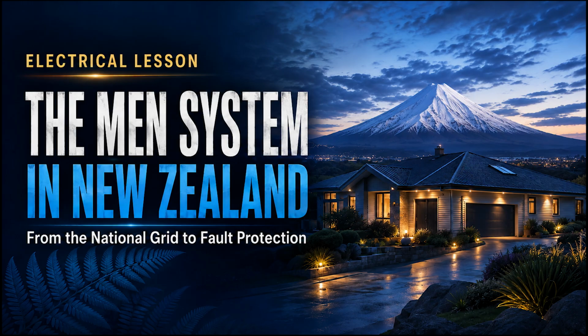Third, an unwanted neutral to earth link at a downstream board. Normal neutral current can flow through the protective earthing system and bonded metal. This can create shock risk, interference, and nuisance RCD operation.